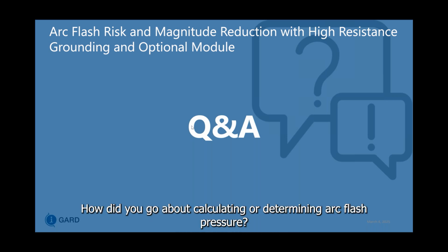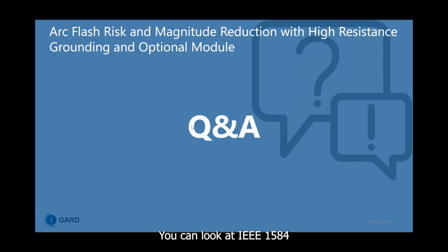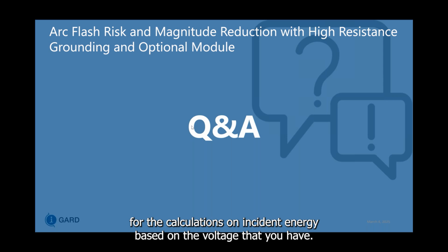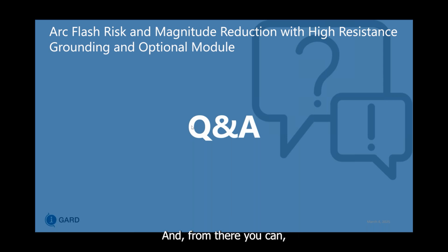How did you go about calculating or determining arc flash pressure? You can look at IEEE 1584 for the calculations on incident energy based on the voltage that you have, and from there you can see how many cal/cm² you would have when an arc flash would occur.